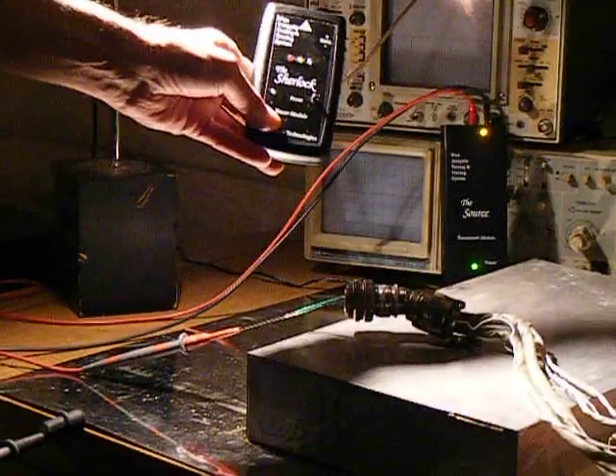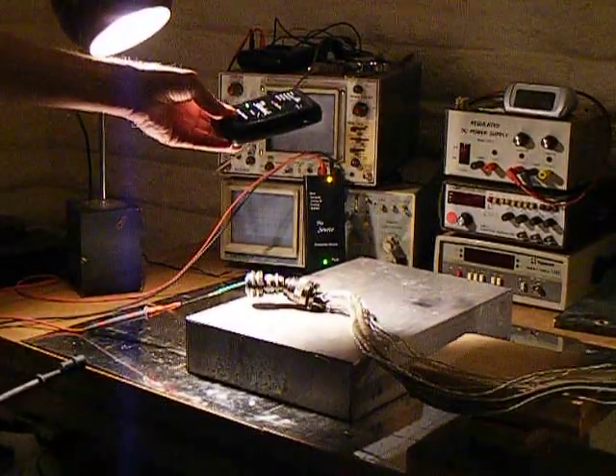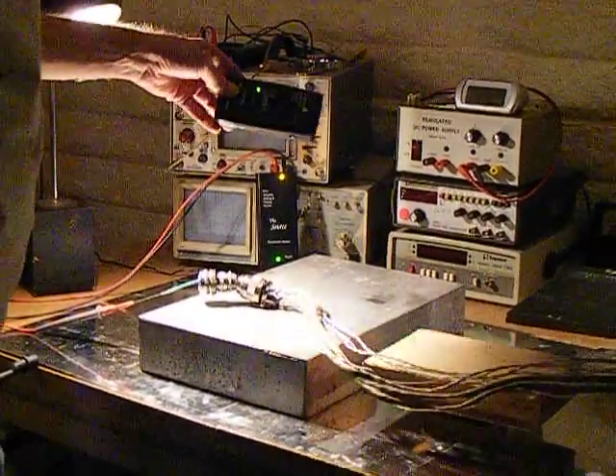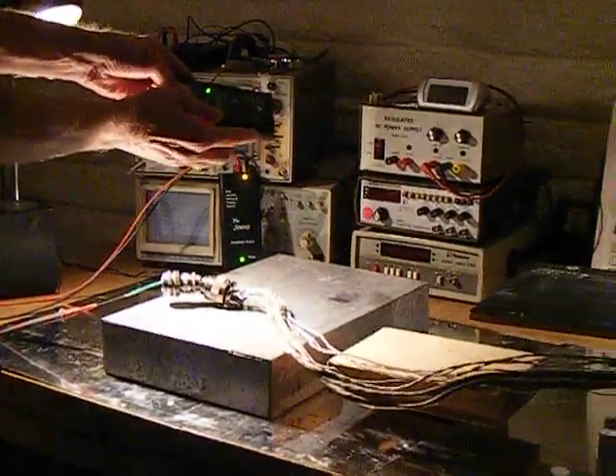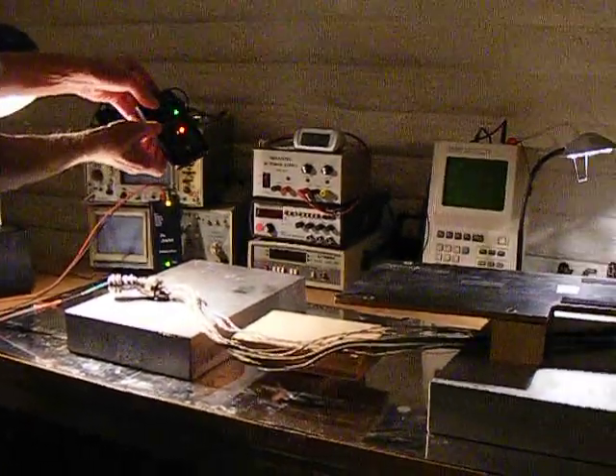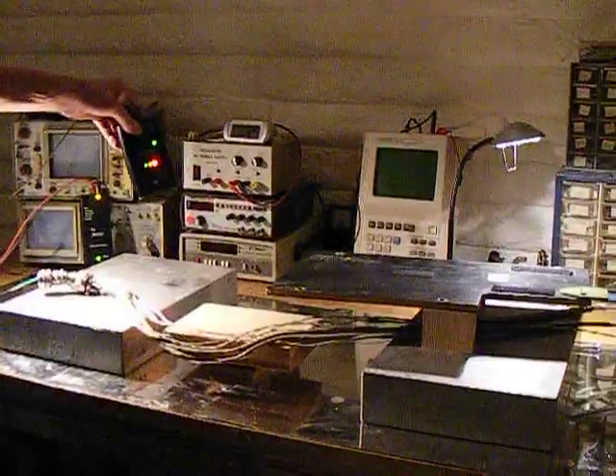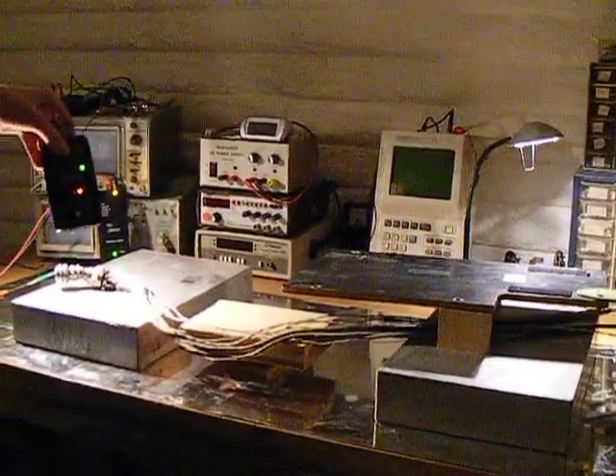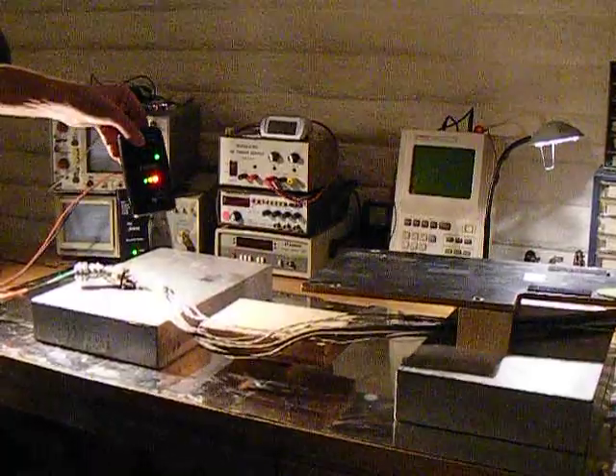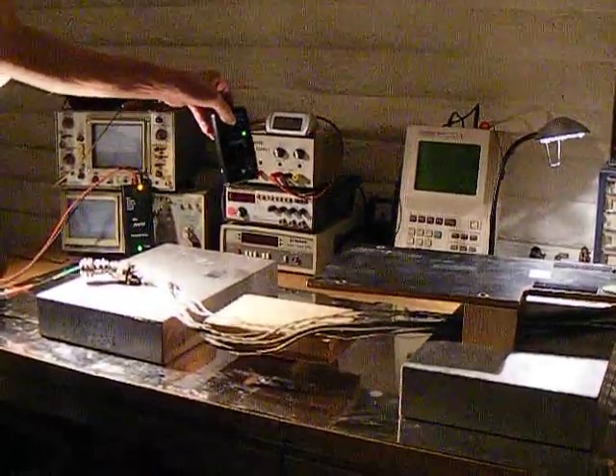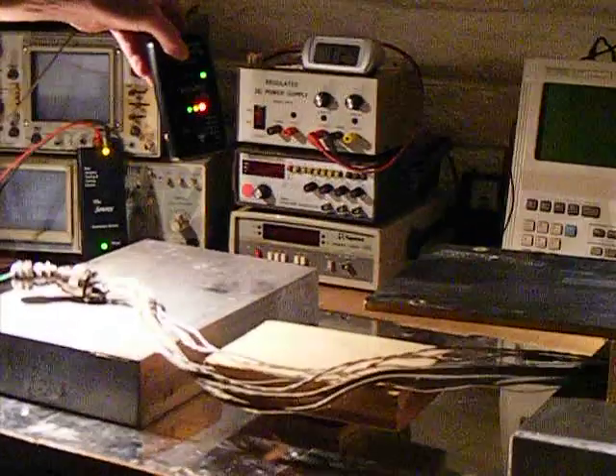Now, we will use our tracer to find where the short exists down the wire. The way this operates is we turn our sensitivity up all the way, and you'll see the red LED light up, amber and green. As we move off of the signal path, the wire which has our reference signal on it, the LEDs fade away.